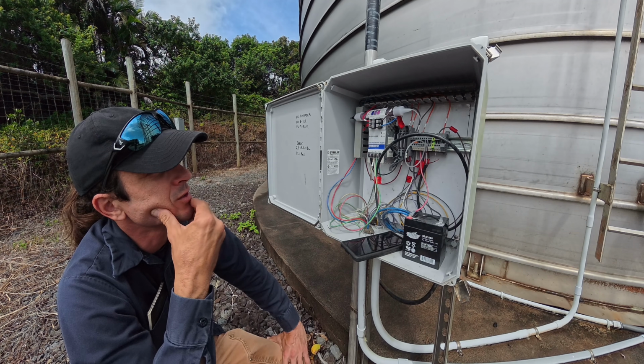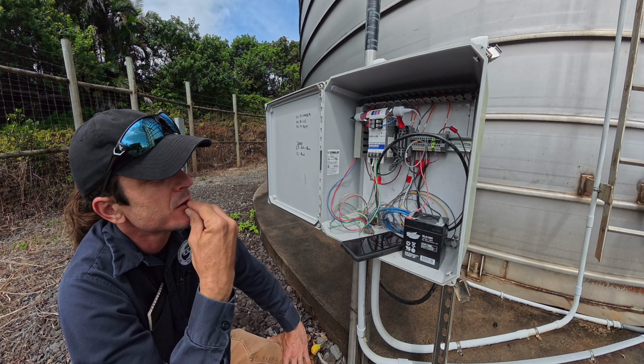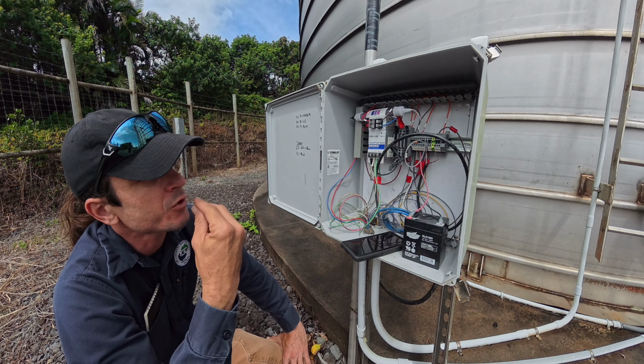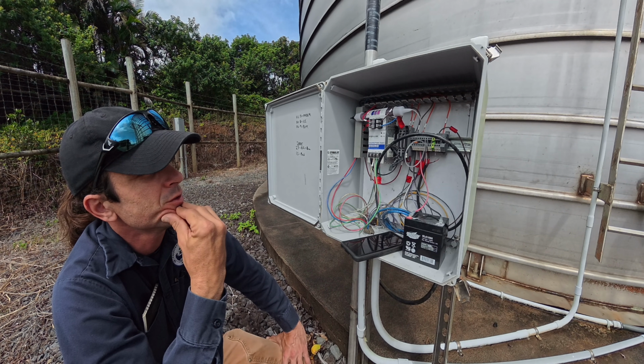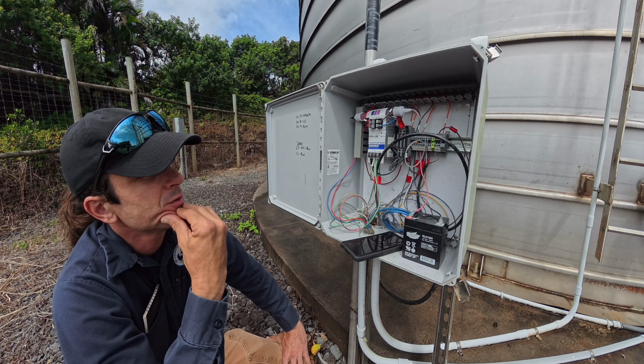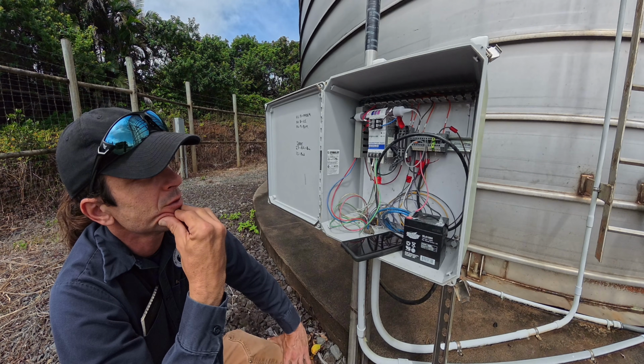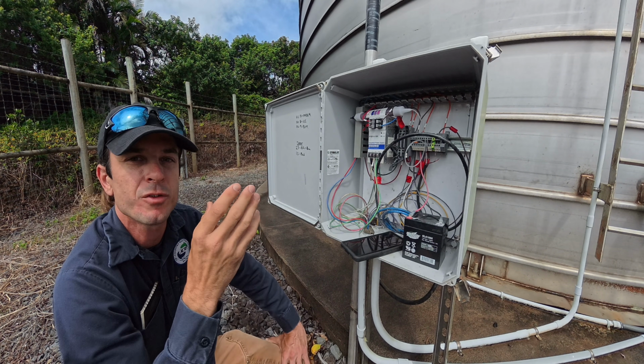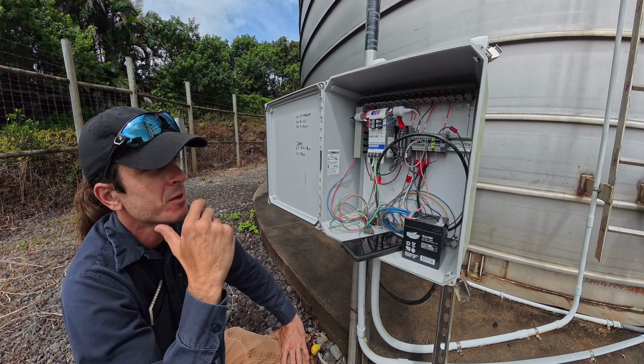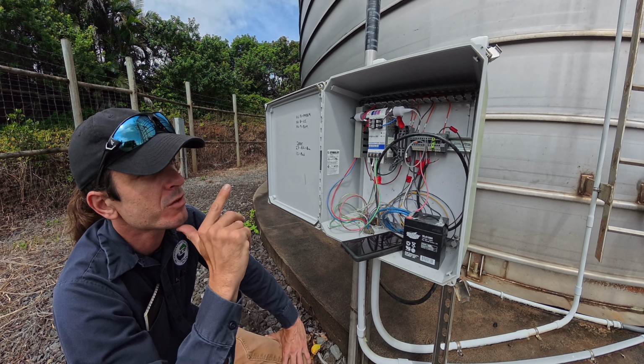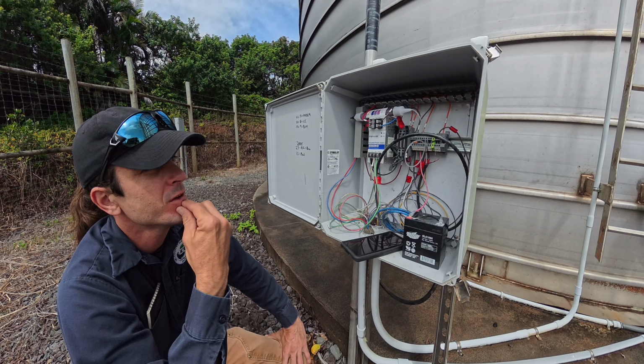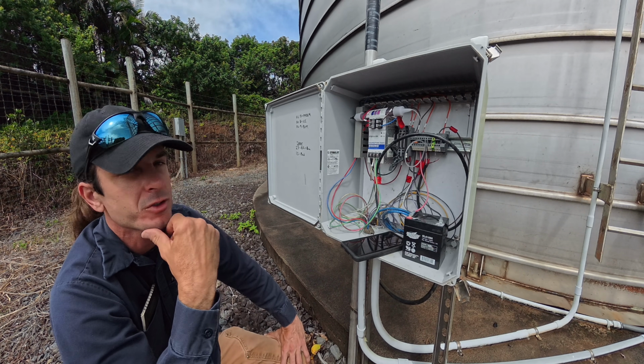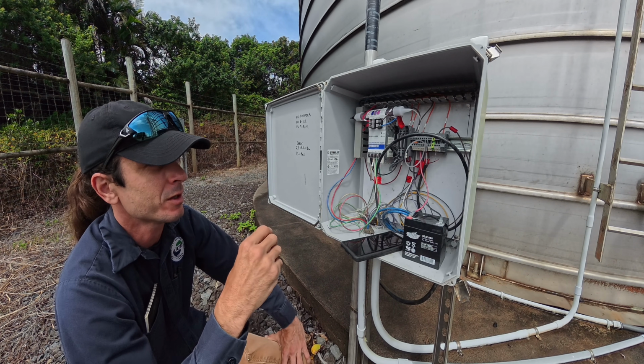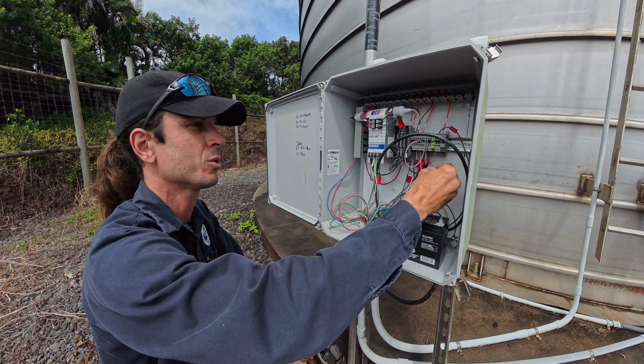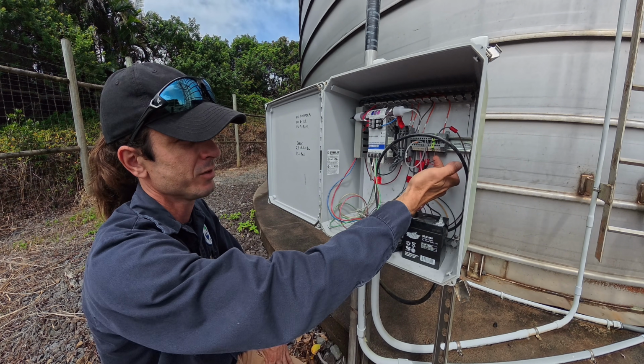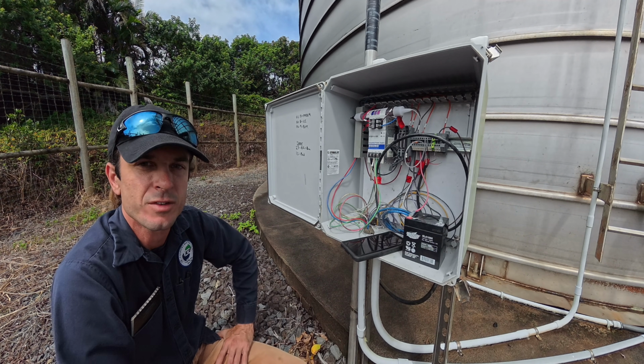The other alternative is removing the shield so that it doesn't short to the shield. Got a few different paths I could take here. I think I'm going to connect to the PLC with my laptop, see what it's seeing live here, and then take the shield off and see if it maintains. I think it's just going to pop a fuse right away though, unfortunately, because of the short between the positive and the shield. Okay, we'll test that out.